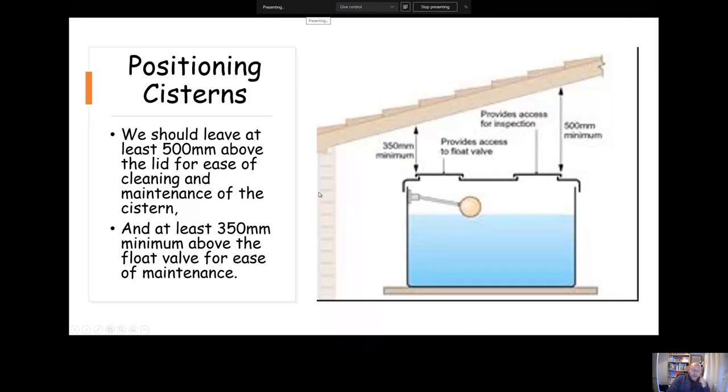When it comes to positioning cisterns, we need to position cisterns carefully. The key sizes with regards to the position: it should be no closer than 350 mil to the roof and that's so we can get into the float valve to maintain it if needs be. Then on the other side, it should be at least 500 mil clearance so we can get into the cistern itself to carry out cleaning.